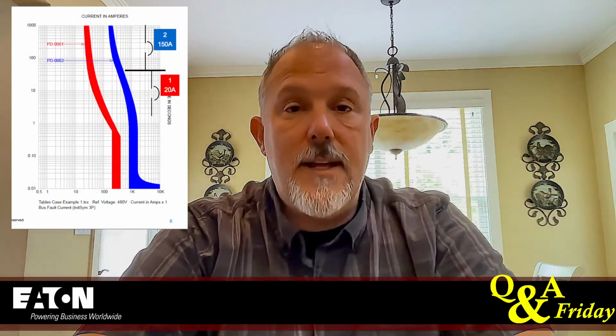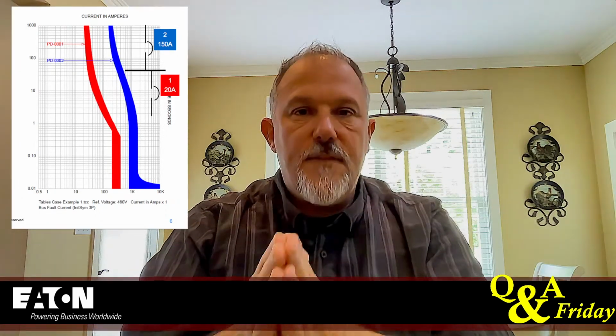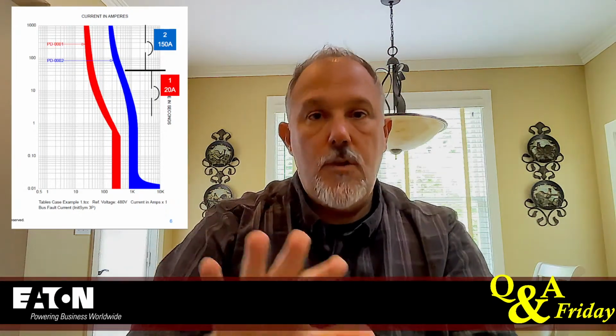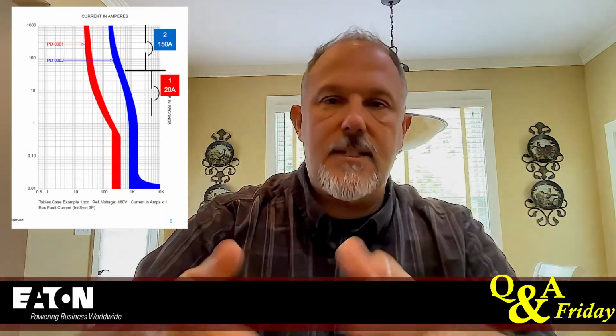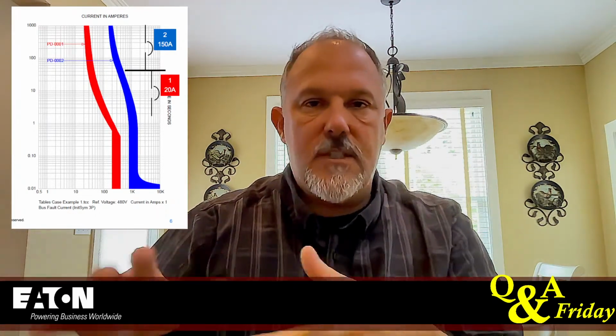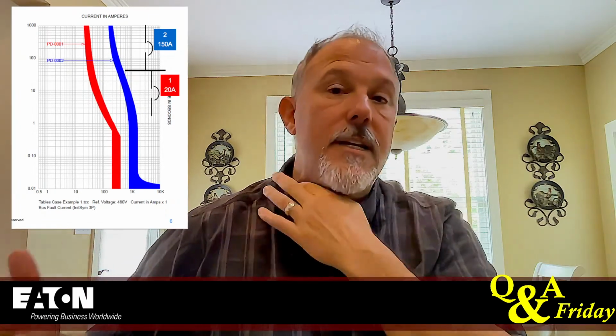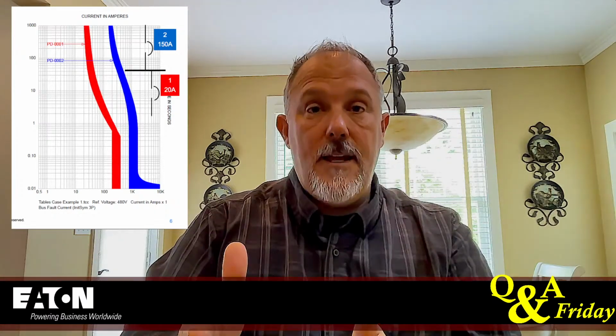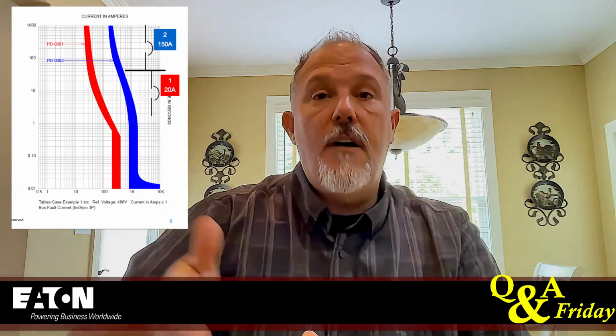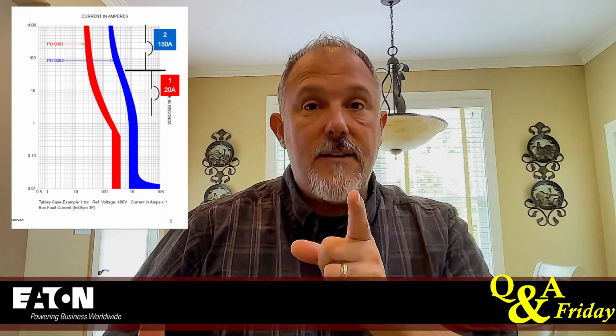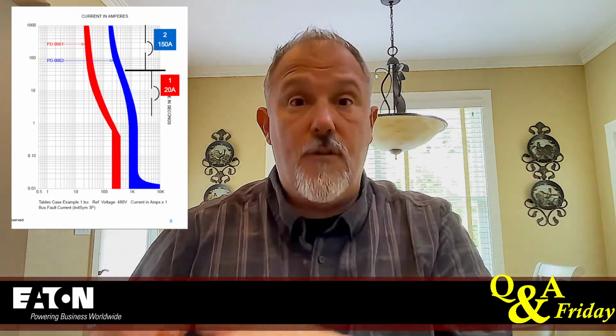If your fault current was 5,000 amps, put it this way. If your bolted fault current for this pair of breakers was 5,000 amps, and you had a bolted fault, you know they both open. If a ground fault... let's say ground fault currents are around 60-some percent. If you look at the IEEE books, your ground fault currents are around 60, 70% of the three-phase bolted fault current. To make it easy, let's just say the ground fault current is 50% of the bolted fault current, which makes that 5,000 amps, 2,500 amps of ground fault current, the most common fault in a power distribution system.